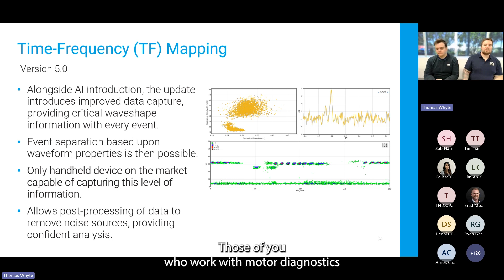Those of you who work with motor diagnostics or other online systems may already be familiar with this approach. This type of feature is unique in the handheld testing world, making the UltraTEV Plus² the only handheld device on the market capable of capturing this level of diagnostic information. The tool provides a platform to separate overlapping events in a signal based on its shape and frequency of the waveform. This means we can more effectively distinguish between different PD sources and background noise, especially in complex or noisy environments where traditional analysis may struggle. I'll show some examples across the next couple of slides.